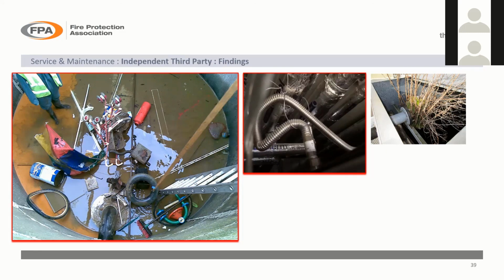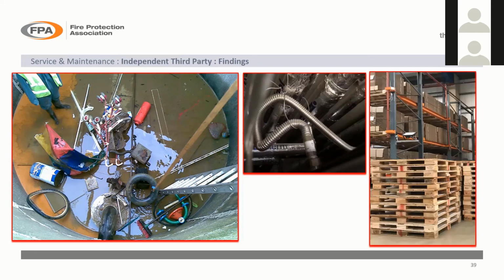Because if that sprinkler head operates, it's a good chance that it will just be ineffective. The head itself might actually be above the ceiling. It's difficult to tell from this picture. And finally, what that shows there is a storage rack, which was a sprinkler rack, all well and good. But there they've stored a lot of pallets, idle wooden pallets, which is a very, very high fire risk.